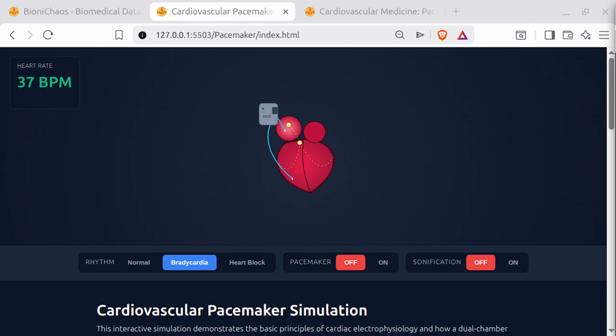Yes, but assuming the navigation goes flawlessly, the leads are secured in the heart. But they don't just plug it in and stitch you up, right? The NIH overview spends a lot of time on what happens next. If we connect this to the bigger picture, everyone's heart tissue conducts electricity slightly differently. The device requires highly specific calibration. Like a tuning process. Exactly.